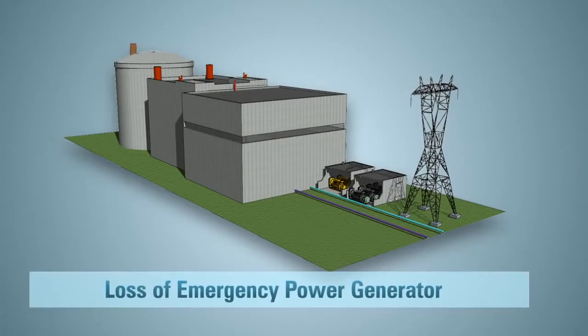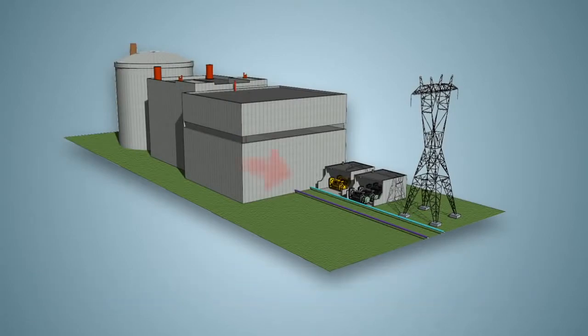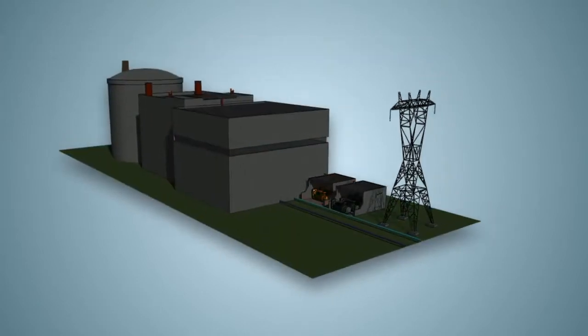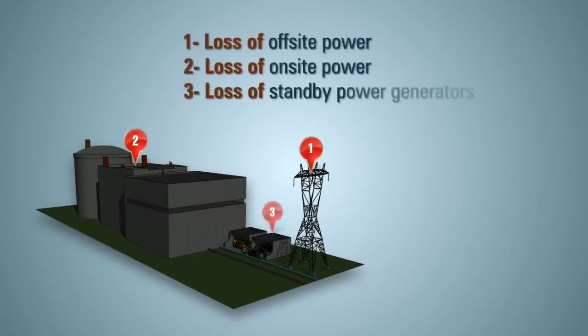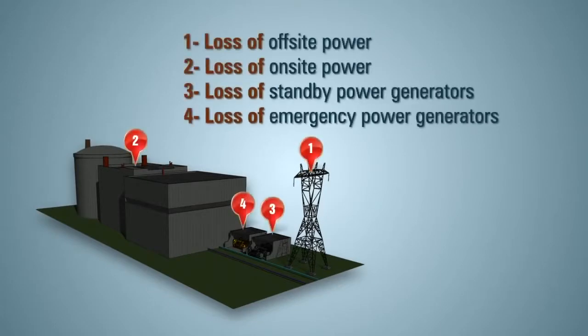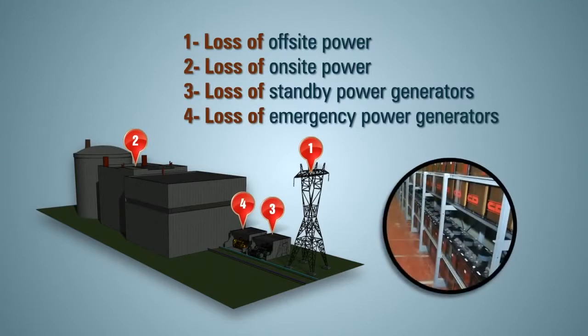Though unlikely, let's keep going and assume the emergency power generators stop working. We now have a total station blackout. This means all power sources used to cool the reactor and spent fuel pool, including off-site power, on-site power, and the standby and emergency power generators are all unavailable. Batteries are now powering emergency lighting and essential instrumentation.